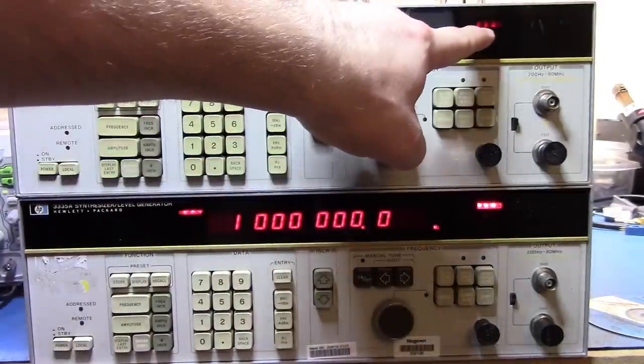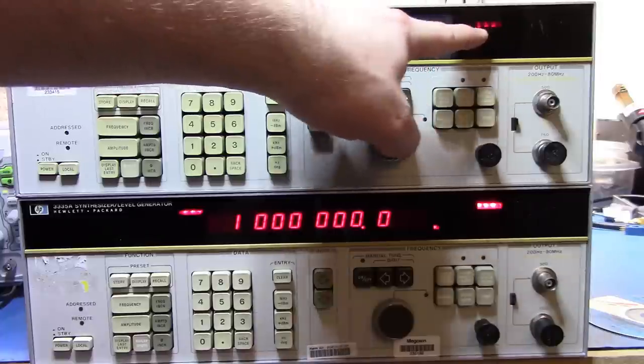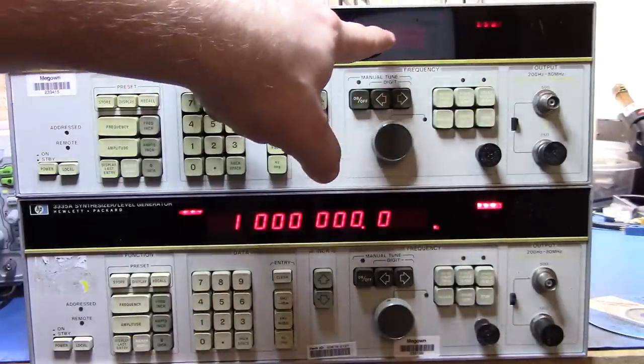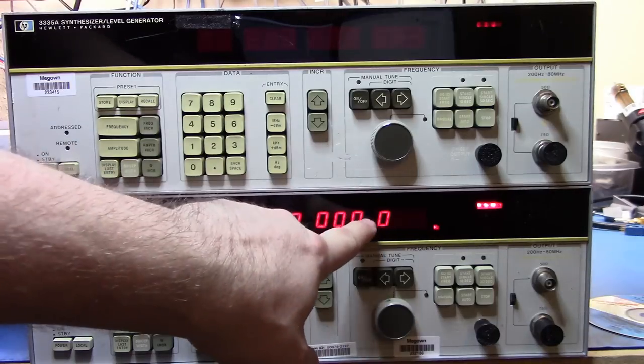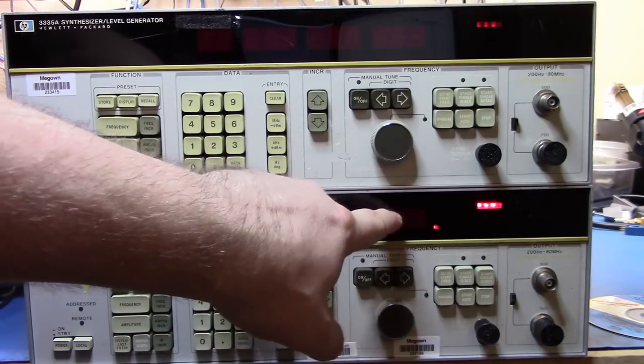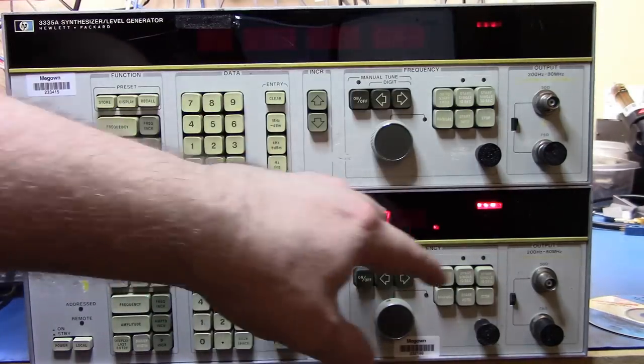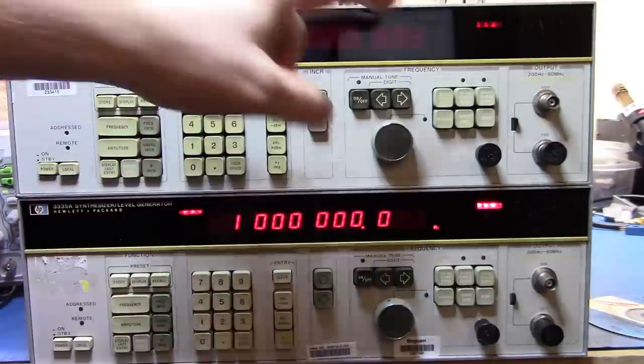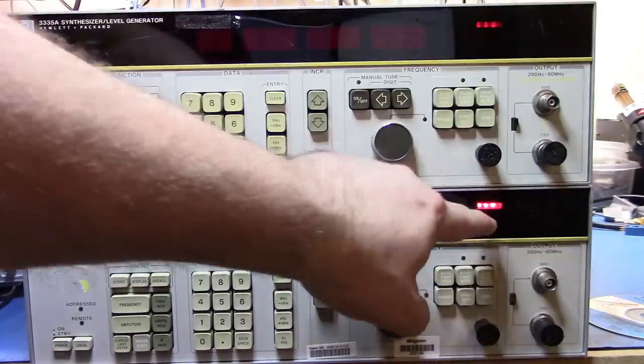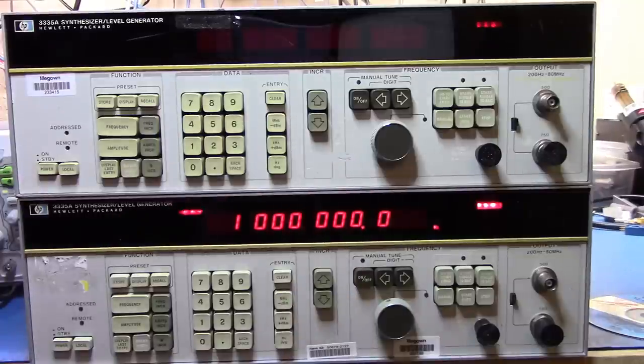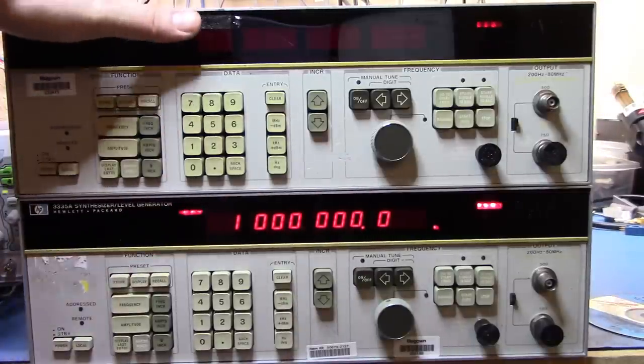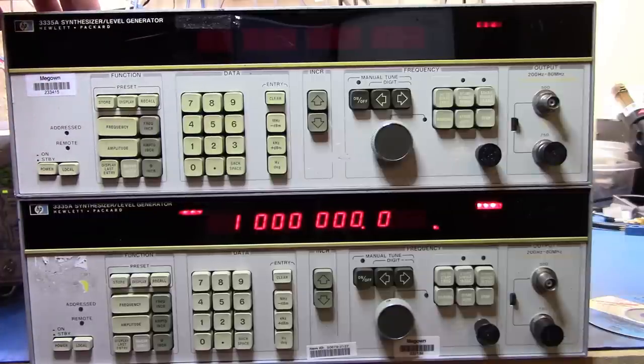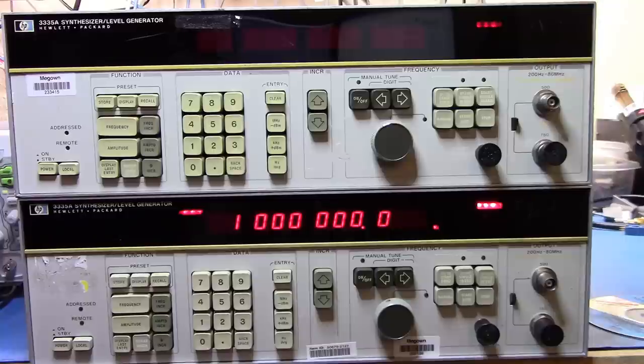We can see very light unlocked come through here. Now it turns out that this little panel here and all these other lights are controlled by the display board or the controller board in here. The unlocked and some of the other lights over here, these annunciators, are actually not controlled by that board. So this looks like it's either got a problem with the power, one of the rails might not be running, or there's a problem with that controller board.